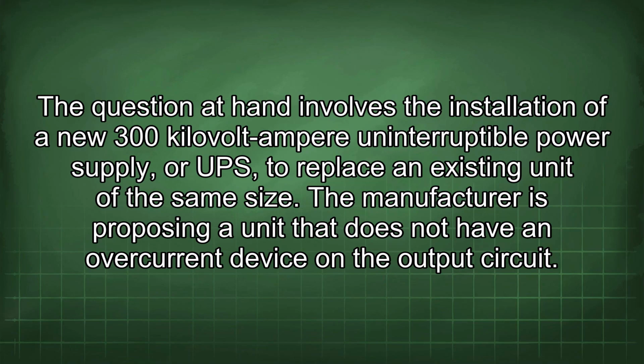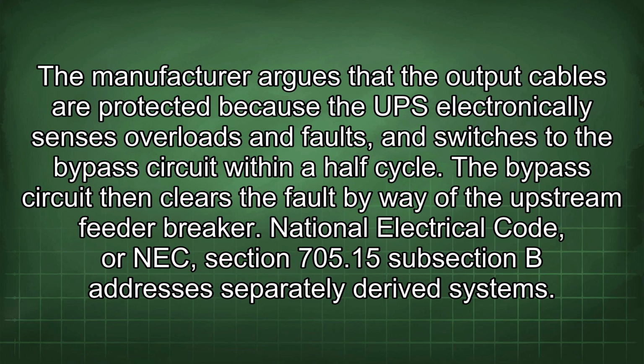The question at hand involves the installation of a new 300 kVA uninterruptible power supply, or UPS, to replace an existing unit of the same size. The manufacturer is proposing a unit that does not have an overcurrent device on the output circuit. The manufacturer argues that the output cables are protected because the UPS electronically senses overloads and faults and switches to the bypass circuit within a half cycle. The bypass circuit then clears the fault by way of the upstream feeder breaker.